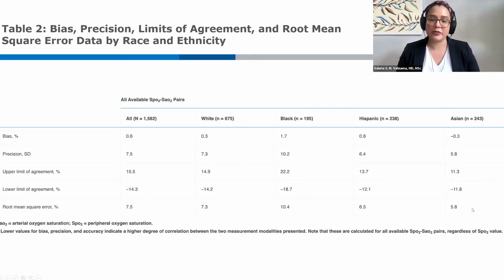You want that value to be as small as possible. Without getting too much into the mechanics, it's a measure of how different the two tests actually are. The FDA calls for a root mean square error of about 2 to 3. That's how different the pulse oximeter gets to be from the arterial blood gas for it to be approved. For the entire cohort, it was about 7.5, and for white patients in the cohort it was similar. But when you look at the root mean square error for Black patients, it's 10.4. So it's quite a bit larger, showing the two tests are not correlating as well for the Black patients in the cohort. This 3-point difference, I think, is hard to ignore.